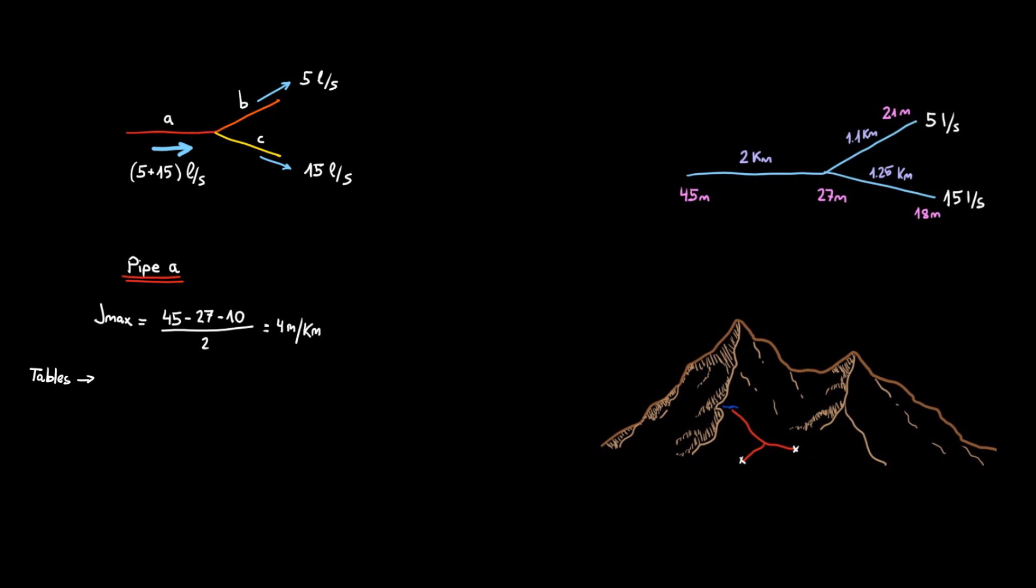In step 3 we calculate the head at the end of the pipe. We started with 45 meters and we lost 3.5 meters per kilometer. Step 4 we calculate the pressure, the head minus the elevation.